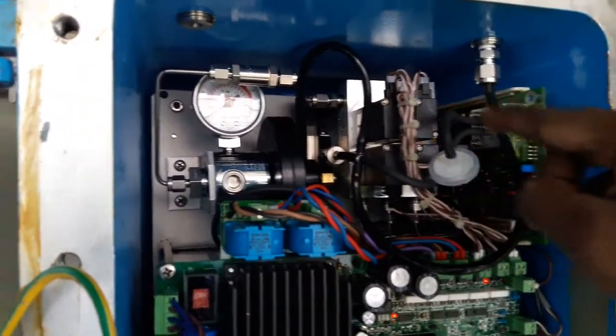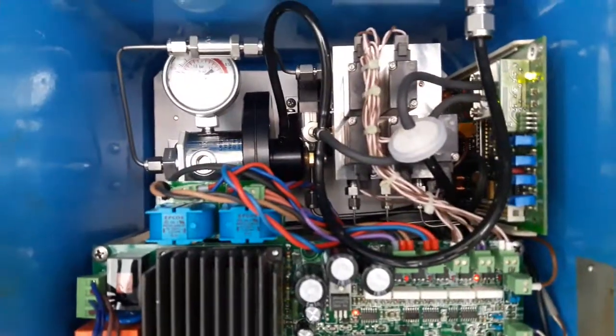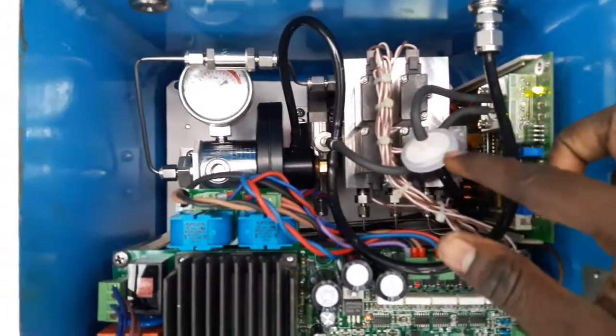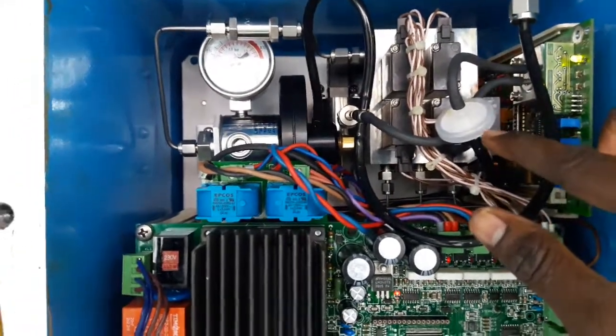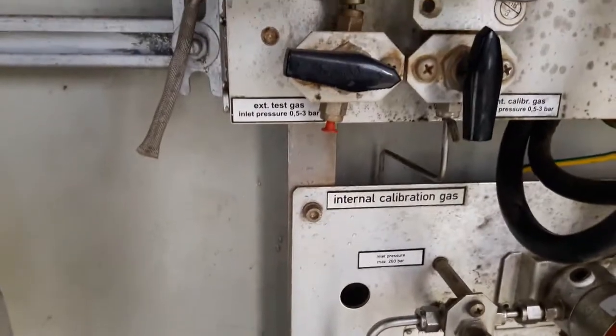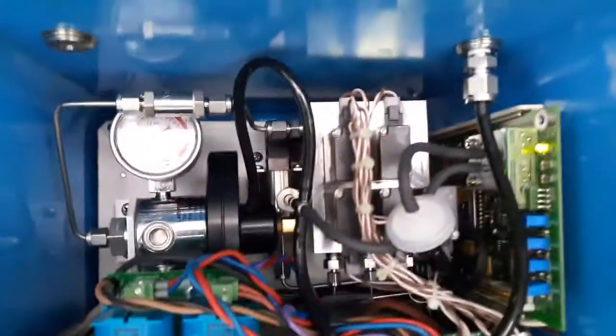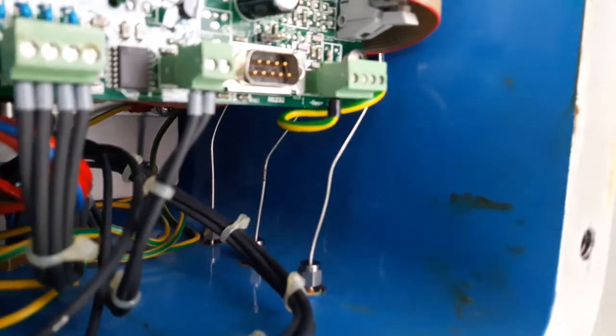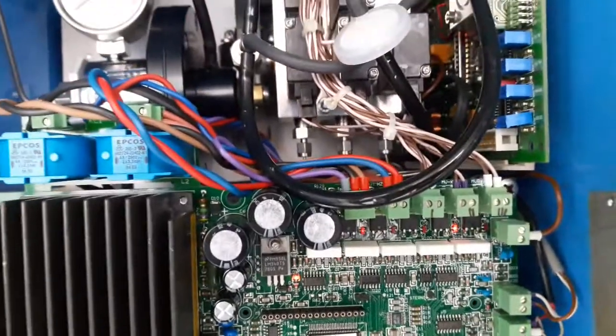And if you see this electronic panel, this PCB has a heater, and those are solenoid coils. Depending on your selection at the analyzer, these solenoid coils will act on which gas it has to take, whether calibration gas, sample gas, or test gas. All are connected to a common exhaust from these different sensors. These three are the lines: calibration, sample and test. And the solenoid coils operate at roughly 8 to 12 volts.